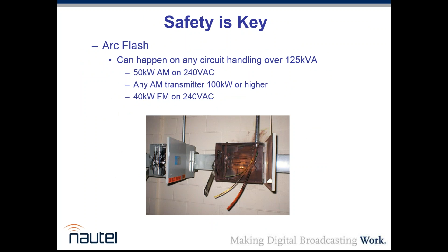Yep. So it is something that a lot of people have a potential liability for, not to mention, like you said, it'll ruin your whole day. Oh, yeah. And every other day that isn't going to follow. So it's really important to determine if that applies to any of your situations and to have that equipment on site. And again, it's one of those things where it could be something as simple as just opening a regular old fuse disconnect and you don't even think about it. I mean, it's something you do 100 times. If there's a lot of current going through it, it could actually draw an arc across there and you can create plasma real quick. Yep. And I mean, if you've got, as an example, a shorted power supply transformer, shorted plate transformer, and you close the breaker, you've got that instantaneous current flow right now. Yep.